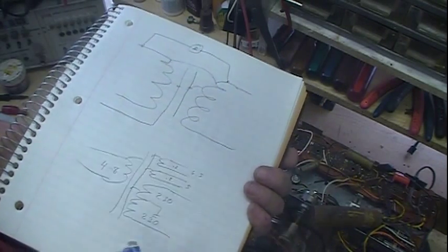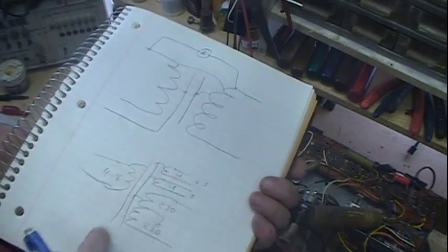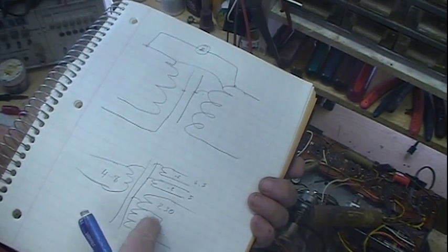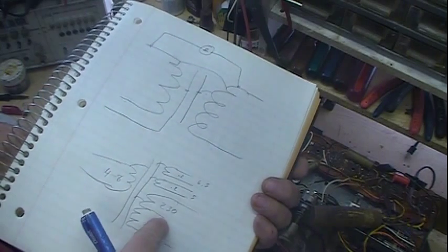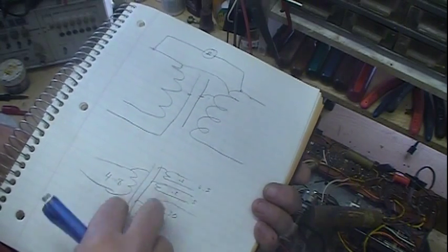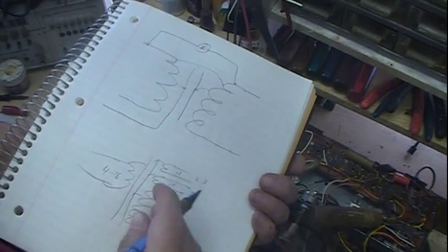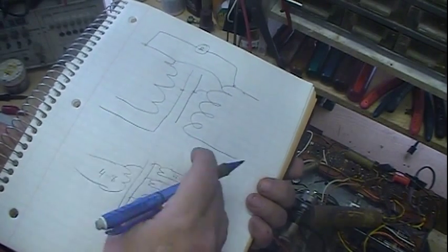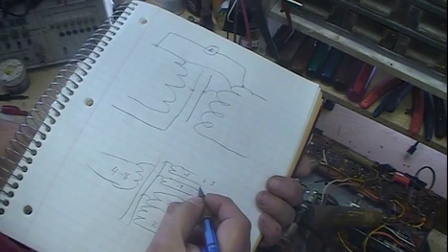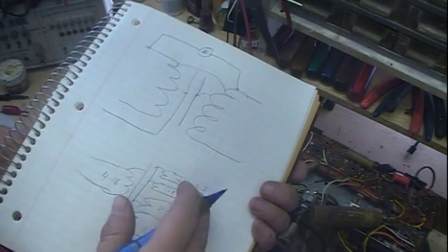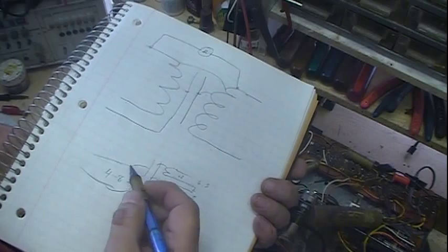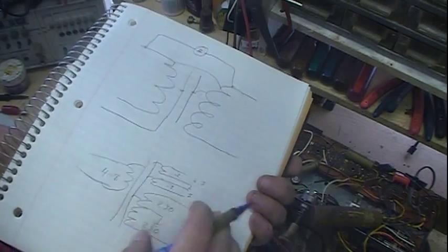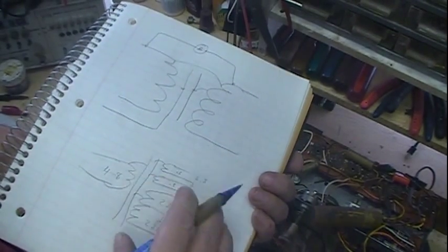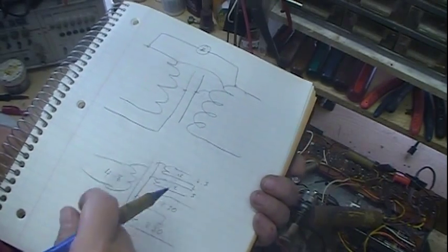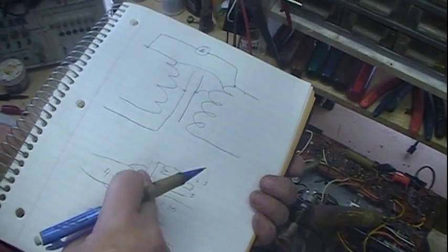The core is what gets bolted to the chassis, so you don't want a ground here, as long as that ground's disconnected. If that ground is still connected onto the chassis, then you'll probably get a read. But you don't want anything here. Now, sometimes the 6.3 might go to ground too, so you've got to be careful with that. But the big thing is you're also going to be checking a lot of the windings, and it's best to disconnect the transformer completely if you suspect any potential shorts, and check it to the core.